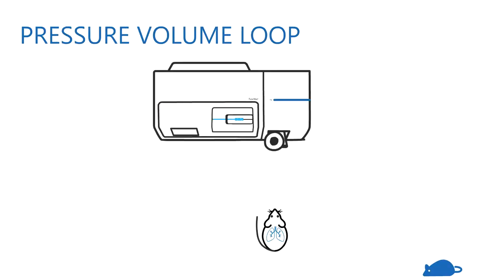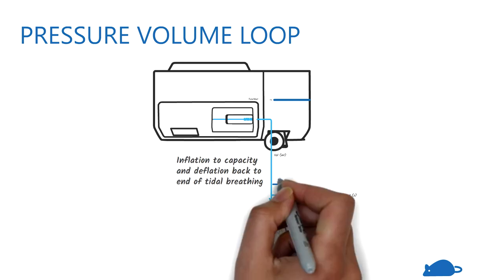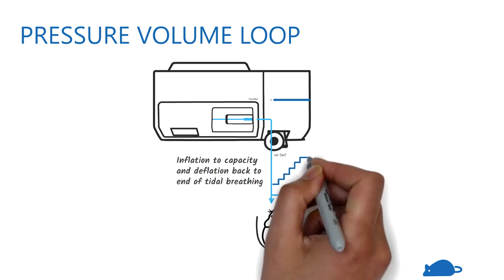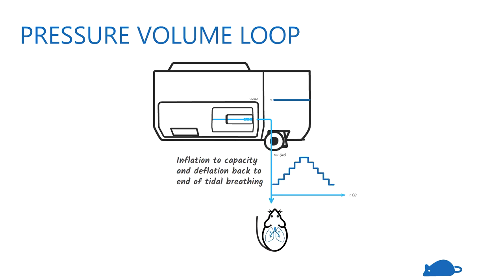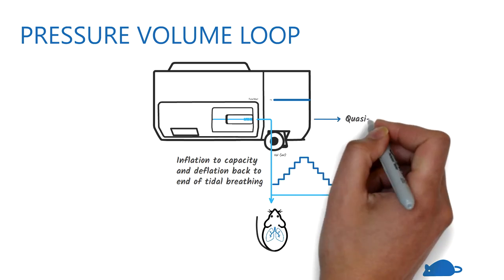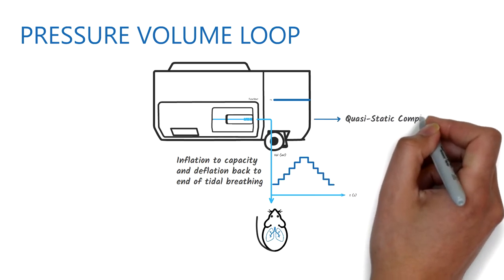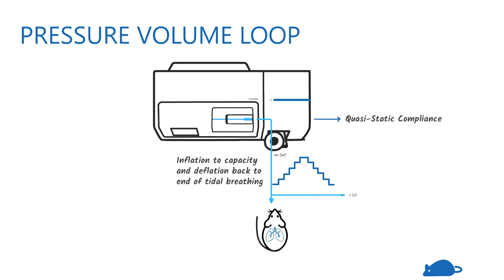In the pressure-volume measurement, the lungs are inflated to total lung capacity and then deflated in a stepwise manner. The flexi-vent measures the quasi-static compliance of the lung across the entire inspiratory capacity.